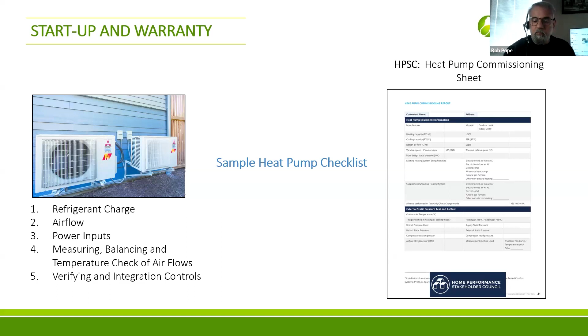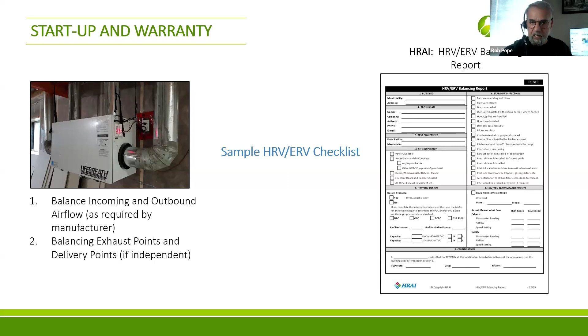If there's an HRV, sometimes it's pretty independent of everything else in terms of balancing requirements, but HRVs are often integrated with forced air systems, so there is some overlap. In either case, there's a checklist or balancing report—this one happens to be HRAI, there's a TECA one as well. Most major manufacturers in this province will also have their own version that's just as complete, covering the balancing of incoming and outbound airflow and balancing at the exhaust and delivery points.